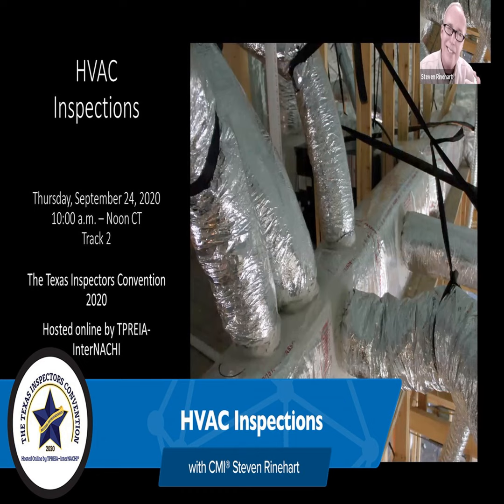Deficiencies in mounting, since we don't have to know all the manufacturer's requirements, you might just be looking at it in a kind of a generalist type view. Is it secure? Not that you go up and yank on it, move it around. Do your best to look at it to see if it looks like it's secured. If you have a question, what's awesome with new little smartphones and pads, you Google that manufacturer right there and you can find out what's in there. Standards say you don't have to know the manufacturer standards. It doesn't restrict you from using those if there's especially a safety issue. Performance issue, yeah. Safety issue, fallout, yeah. Go by the manufacturer.